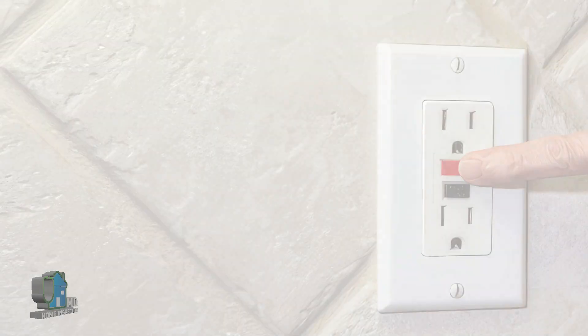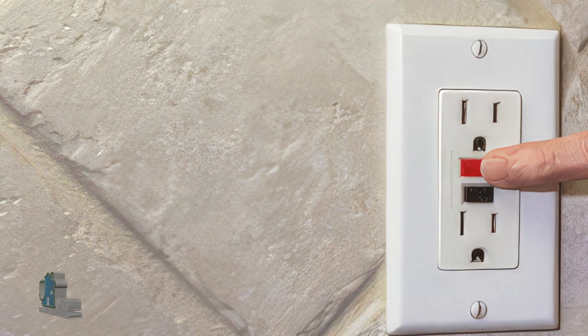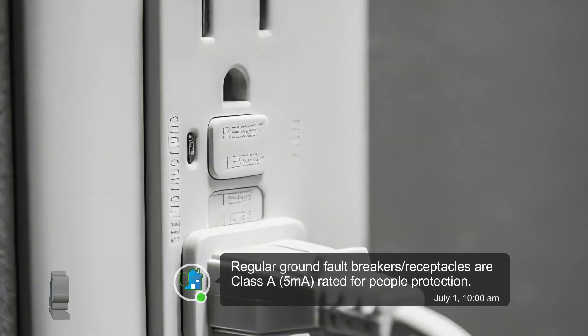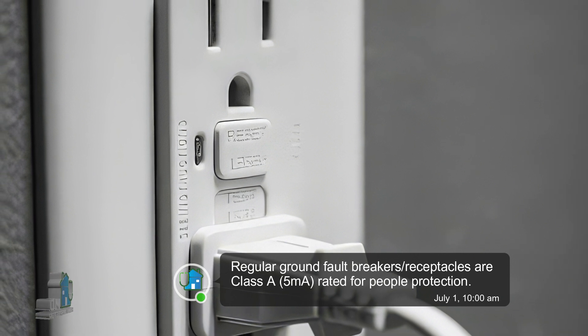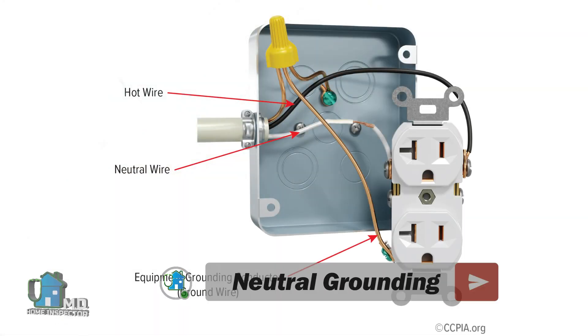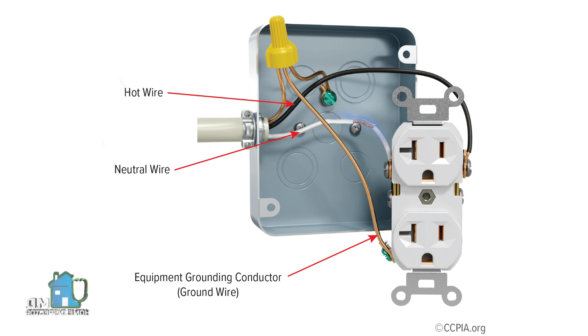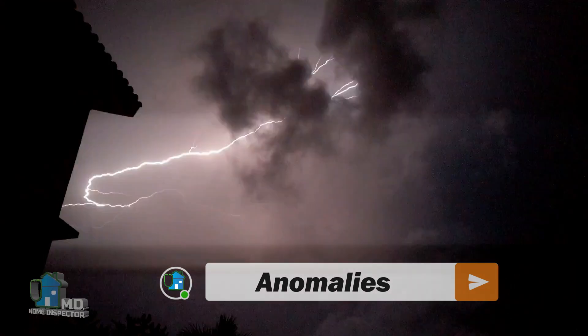An AFCI can also trip from a ground fault — but this is not the same as a GFCI receptacle. A standard GFCI trips at around 5 to 6 milliamps, sufficient for people protection, while an AFCI will detect a ground fault of 30 milliamps or greater. It will also trip on an unintended neutral grounding, such as when the neutral conductor of a circuit touches a grounded metal like a grounded outlet box.